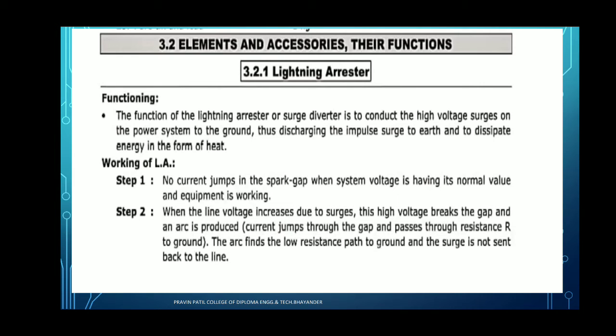Next we have to see the elements and accessories. Also we have to see the function, how it operates and what the function of that accessory or device is. The first one is the lightning arrestor. The function of the lightning arrestor, or surge diverter, is to conduct the high voltage surge on the power system to the ground, thus discharging the impulse to earth and dissipating the energy in the form of heat.